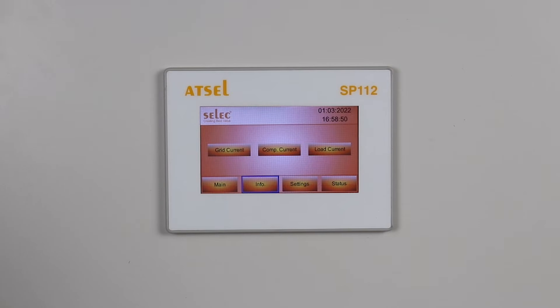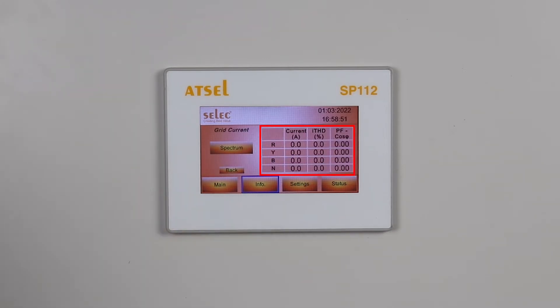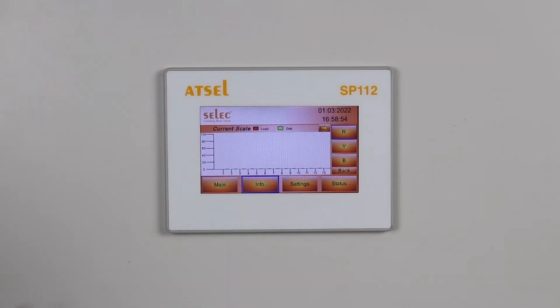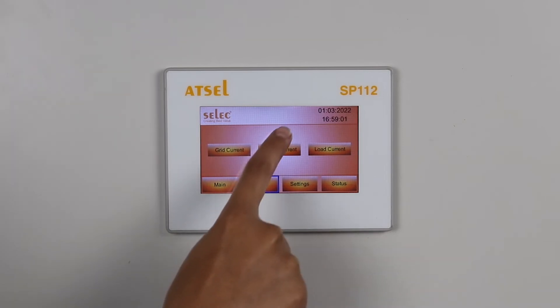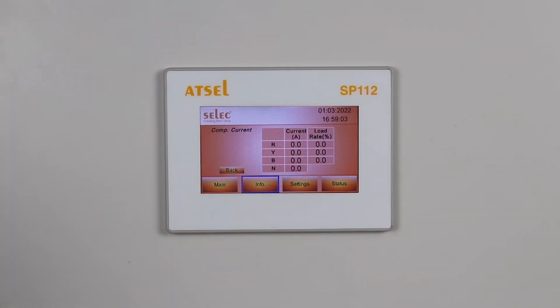In current, you have 3 options: grid side current, compensation current (that is, current supplied by this module), and load current. If you go to grid side current, you will get all 4 phases — RYB and neutral current — their total harmonic distortion and power factor. You will also be able to see the spectrum. In compensation current, you can see RYB and neutral value, current, and its load percentage.